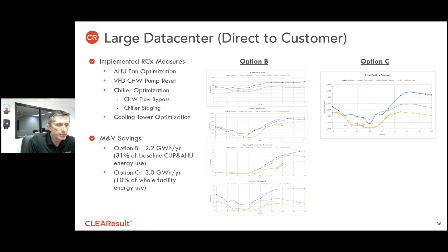In these series of graphs, in the middle, option B is where through measurement and verification we looked system by system at how much was saved individually. Adding those together came up with about 2.2 gigawatt hours per year of savings. However, looking at that across the whole facility meter, which better considers interactive effects and effects even outside of those specific systems, we found it actually had saved 3 gigawatt hours per year, about 10% of that whole facility's energy consumption.